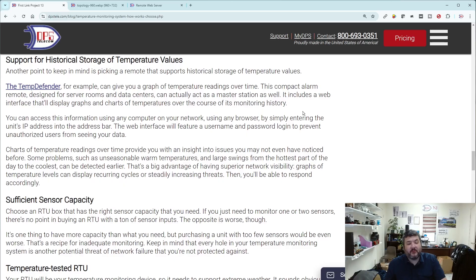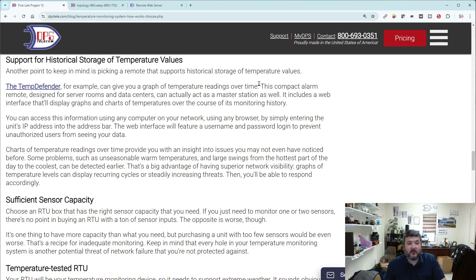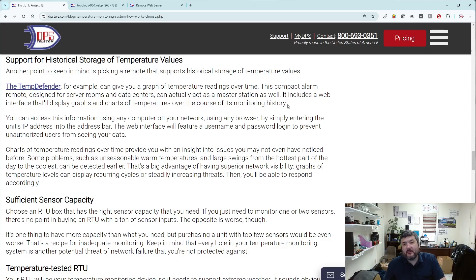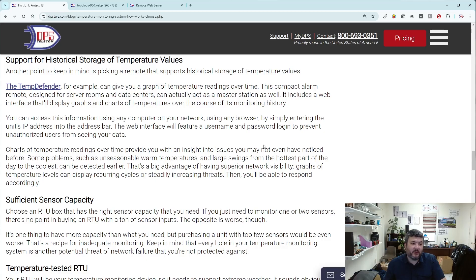There's also historical storage of temperature values. Look for devices that can log to a CSV - it goes to internal memory and at some point you can download a CSV. We have some remotes that will give you a URL that a cron script can access. If you're a savvy IT team and you think in terms of cron scripts and logging things to an SQL database, we can support that as well. Just look for whatever you need as far as historical storage. It probably isn't going to be on the RTU forever. You're probably going to ship it out to some kind of central manager, an SQL server, some kind of long-term storage, because RTUs typically have enough capacity to store a couple thousand readings, but they won't store everything that's ever happened in the last few years.